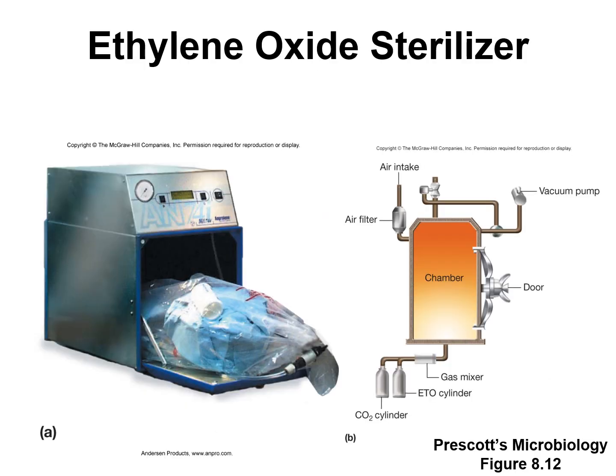And then here's just a smaller ethylene oxide sterilizer. You put your packs and things in there, and then the gas is piped in, and it takes a couple hours to run a cycle. It's run at low temperatures, so it's not going to melt plastics. Then you have to make sure that all of the gas is removed, so it takes a while to make sure that everything's been aerated out before you open the door, because you don't want to be breathing in any of that ethylene oxide gas.